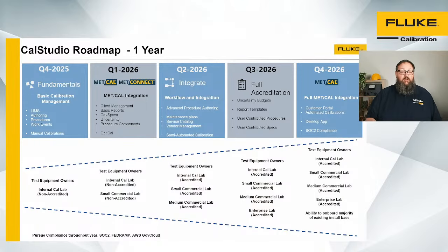So talking about instrument communication specifically, where we're going to start in Q2 of next year is with communication through serial, USB, Bluetooth, all through the browser. One of the really cool things going on right now technology-wise is that unlike in the past, where you had to have something installed on your laptop to communicate with instrumentation, there is new technology with the Web Serial API where we can actually talk to devices through those interfaces directly from the browser. So from within CalStudio, running in the browser, we can talk to those types of devices, and that's where we'll start.